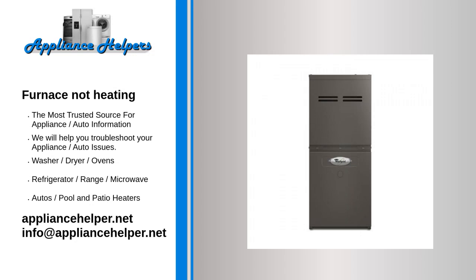The furnace is not heating. Igniter. The igniter gets very hot and glows bright orange to light the gas burner. If the igniter fails or cracks, the furnace won't heat. To determine if the igniter is faulty, remove the igniter and inspect it for cracks.